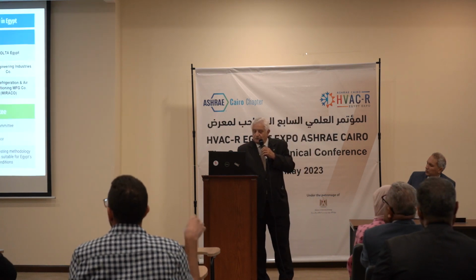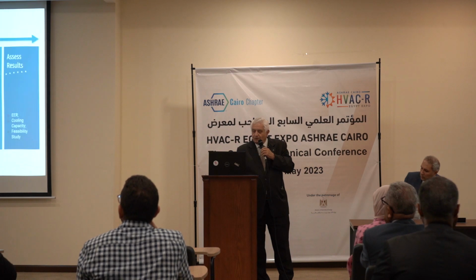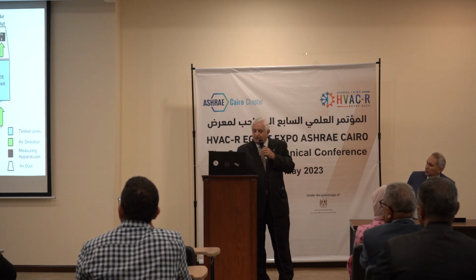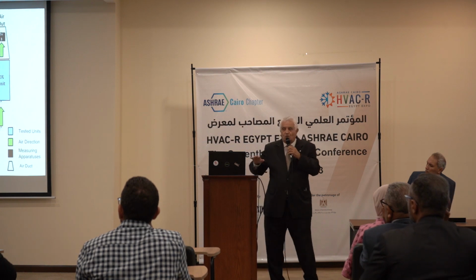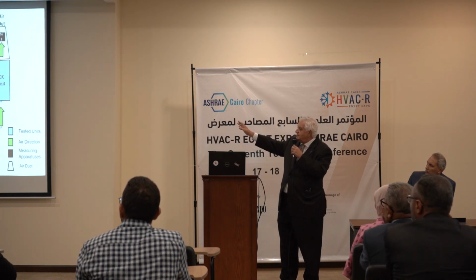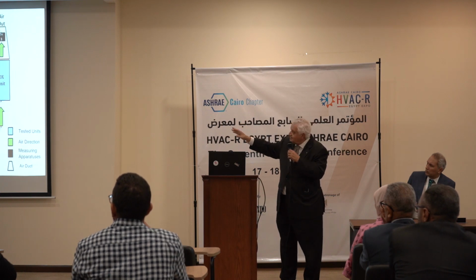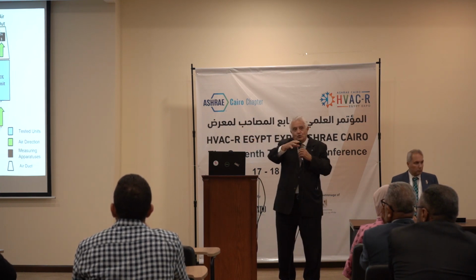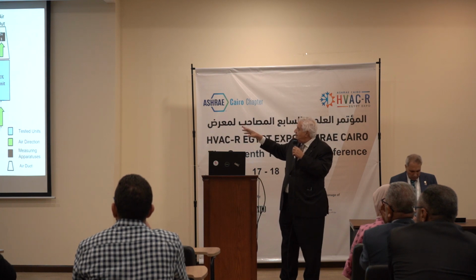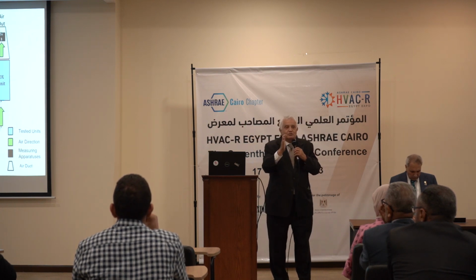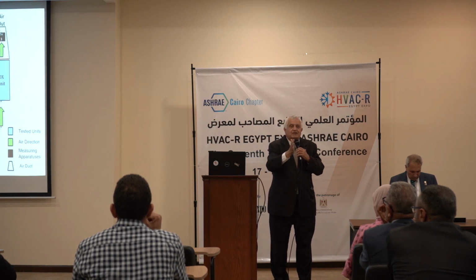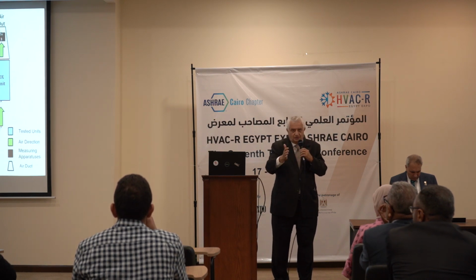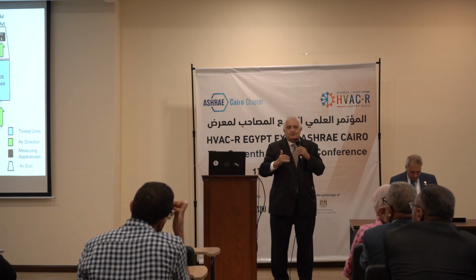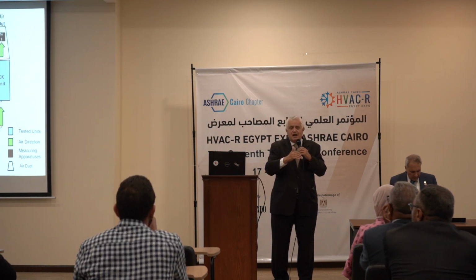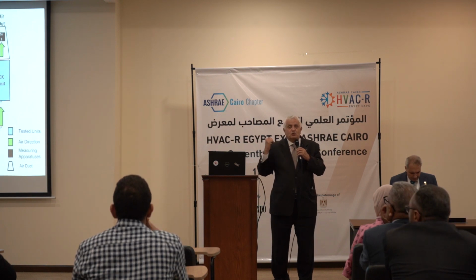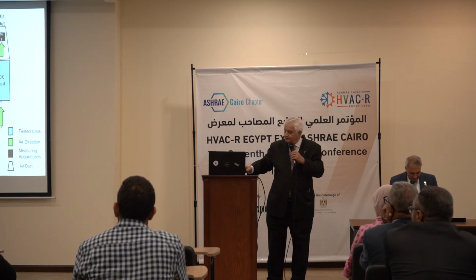So those are the figures that more or less I talked about. And this is how the machines were stacked, one next to the other. On the right is the DX machine. On the left is the IEC machine. And Sally and her group took all the results. And we made sure that both machines operate at the same CFM, at the same rate of discharge, by using a variable speed drive on the IEC unit to match the DX unit. Both units are air-cooled.